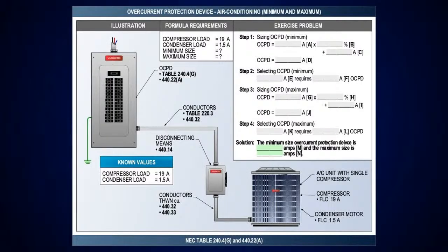One thing I want to mention too is when you're sizing on these AC units, all you have to cover is the minimum circuit ampacity. So if it says a minimum circuit ampacity of 21 amps, you think, oh man, I can't put a number 12 on there. That's not true because the AC unit has 75 degrees C terminals. So all you have to do is go to that 75 degrees C column, and then you just go to that value, which number 12 is good on THHN for 25 amps, and then you can use a number 12 over 20 amps as long as you're in that 240.4(G) column with the AC unit. Sure. And one other thing I want to point out is some will say, why didn't you go over and use the tables in 430.247 through 250? The reason is because this is an assembly. All right.